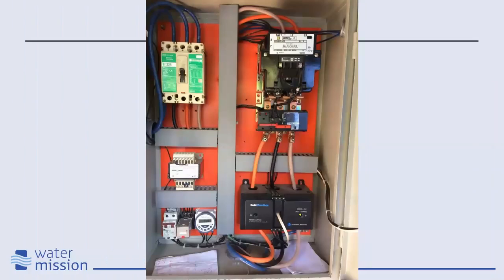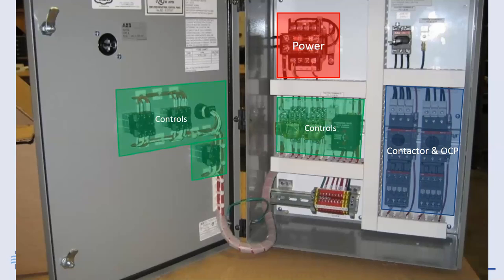Now there's actually a few other components in here that are worth mentioning. Another safety component is this right here. This is a switch, and you can't see it in this photo, but there's a long rod that extends on it right here towards us as we're looking at it. And that rod actually goes into the door right here. There's a big switch on the back side that forces the operator, before they can open this panel, to turn off this component right here, which de-energizes the system, making it safe.